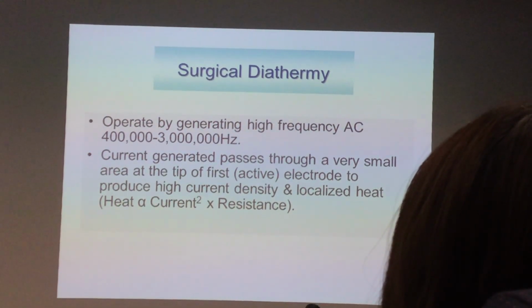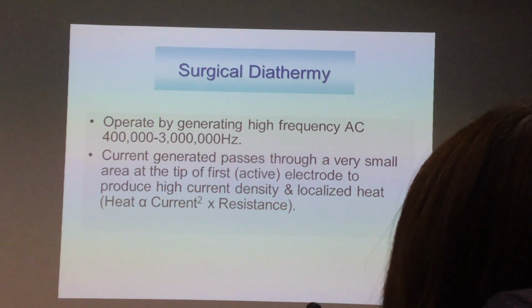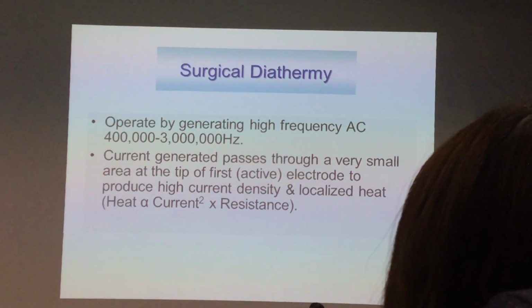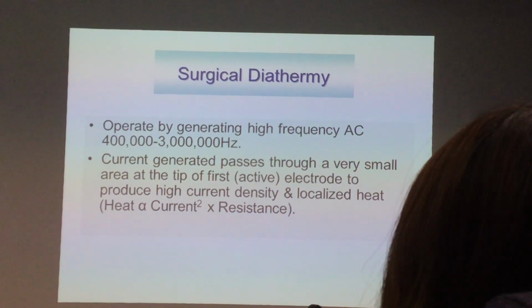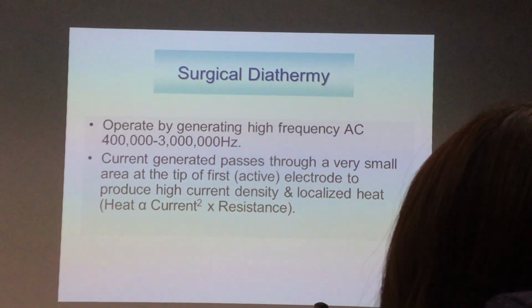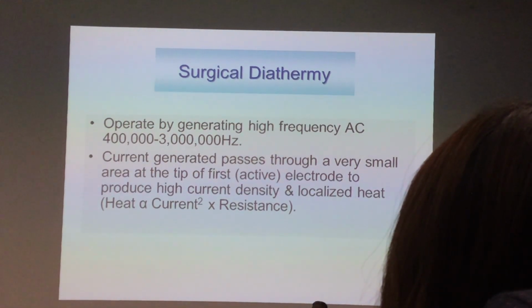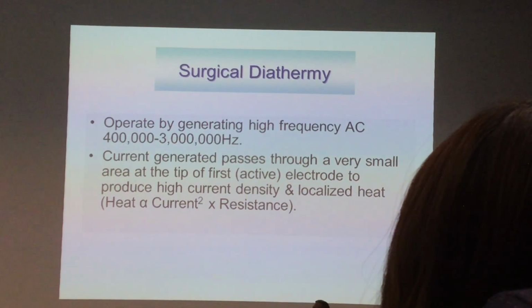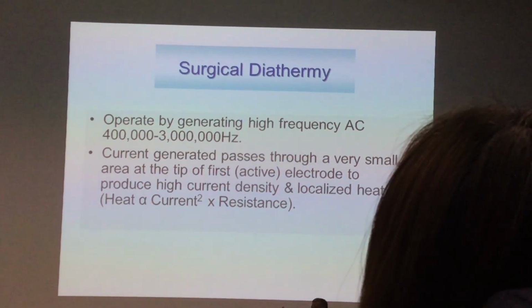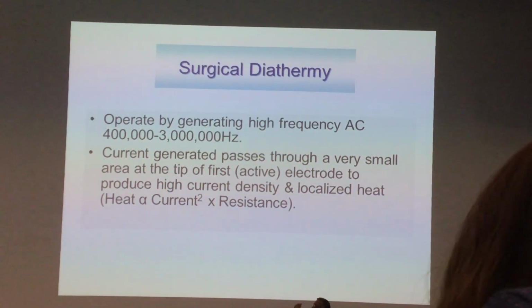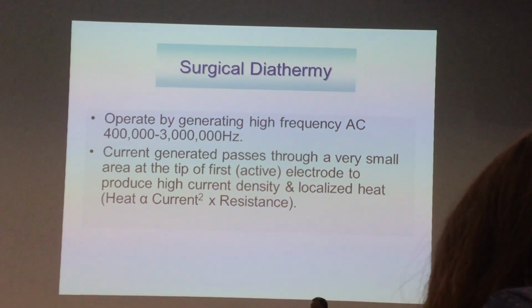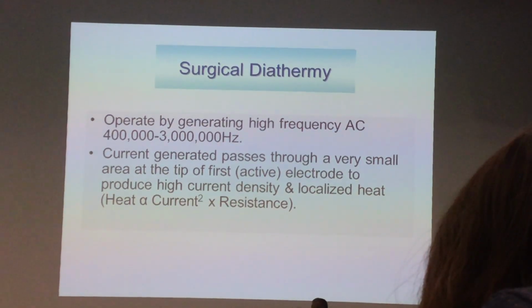Surgical diathermy won't cause electrocution or electrical hazard, because the voltage is 240, but the frequency is not 50. The frequency is up to 3 million hertz. As I said, if the current flow is very fast, up to 3 million hertz, it won't cause any harmful effect to the person. If you use 240, 50, you touch, you go, right? You touch it like fire. But if you use 240 with a frequency of 3 million hertz, you touch, you smell, which means the amount of current that goes through your body to cause harm depends on voltage, number 1, and number 2, the frequency.